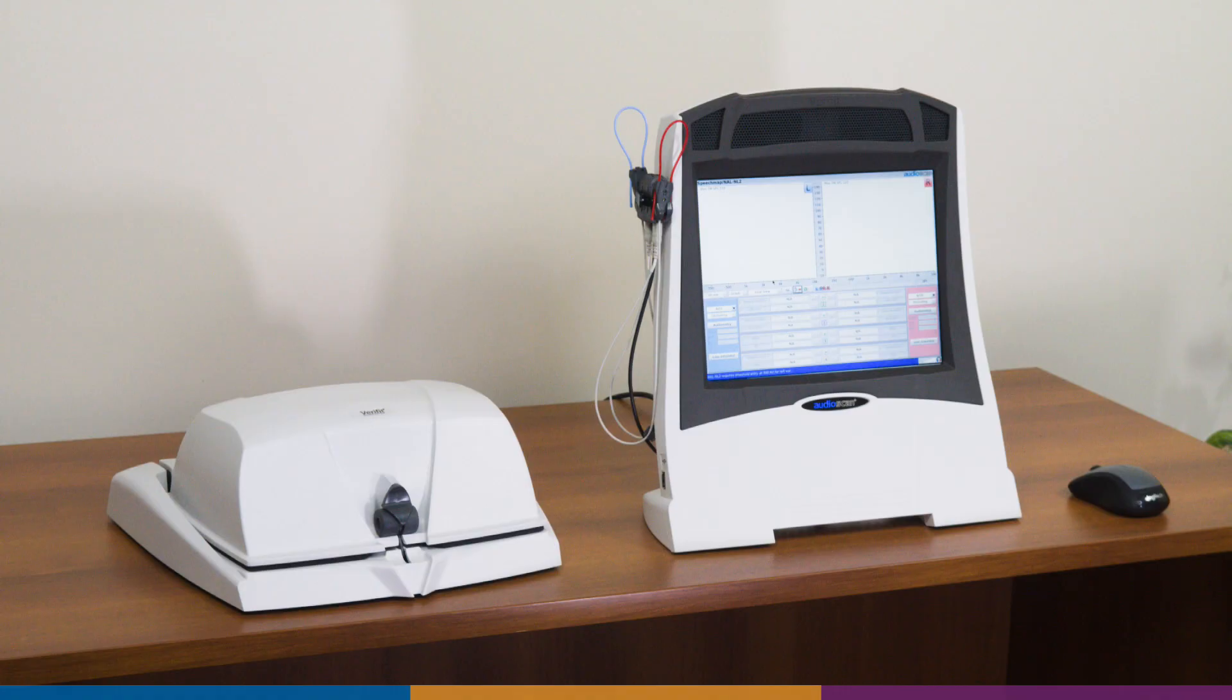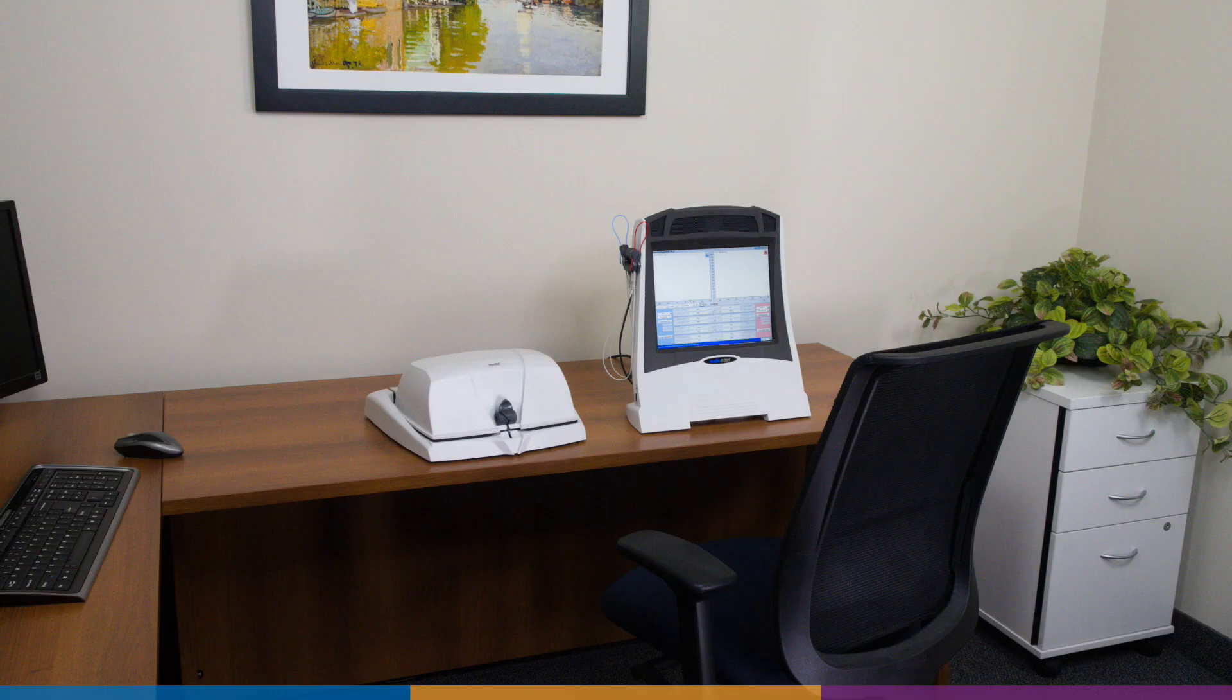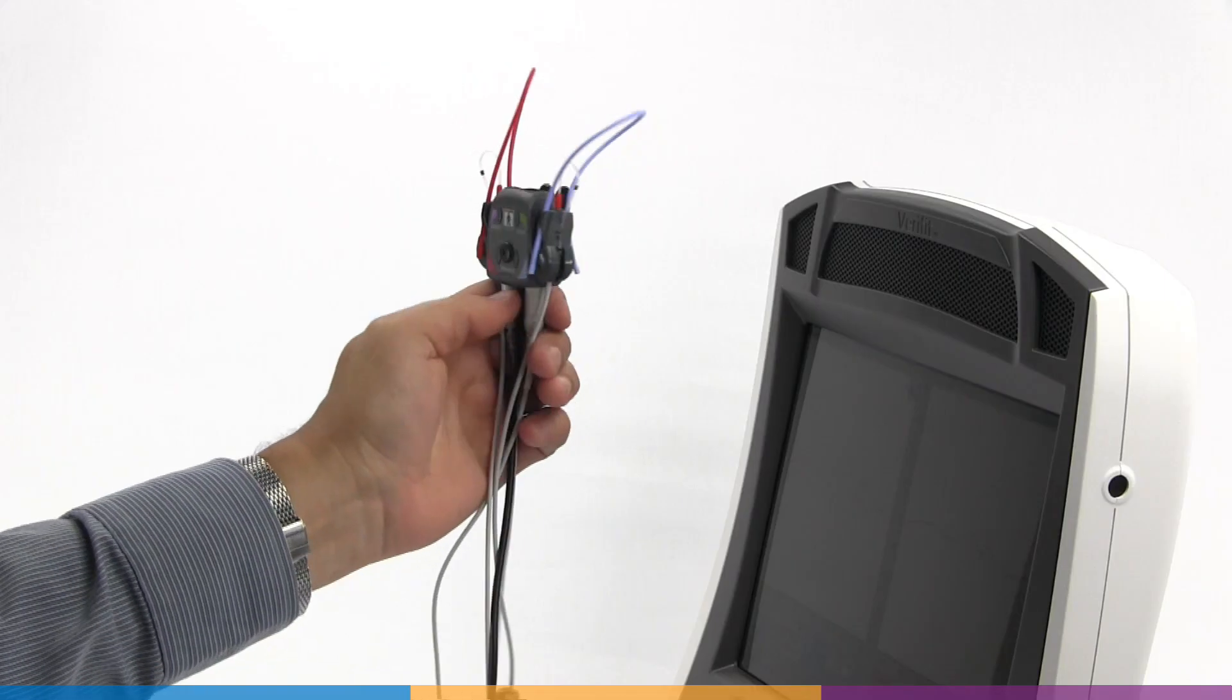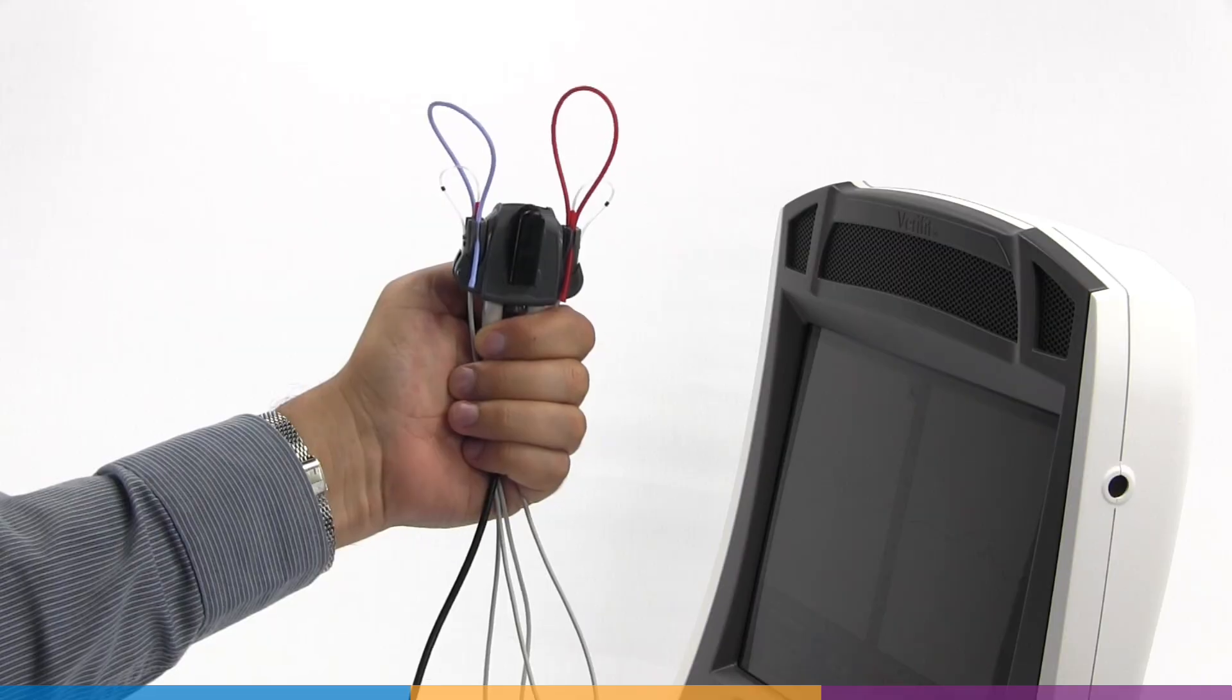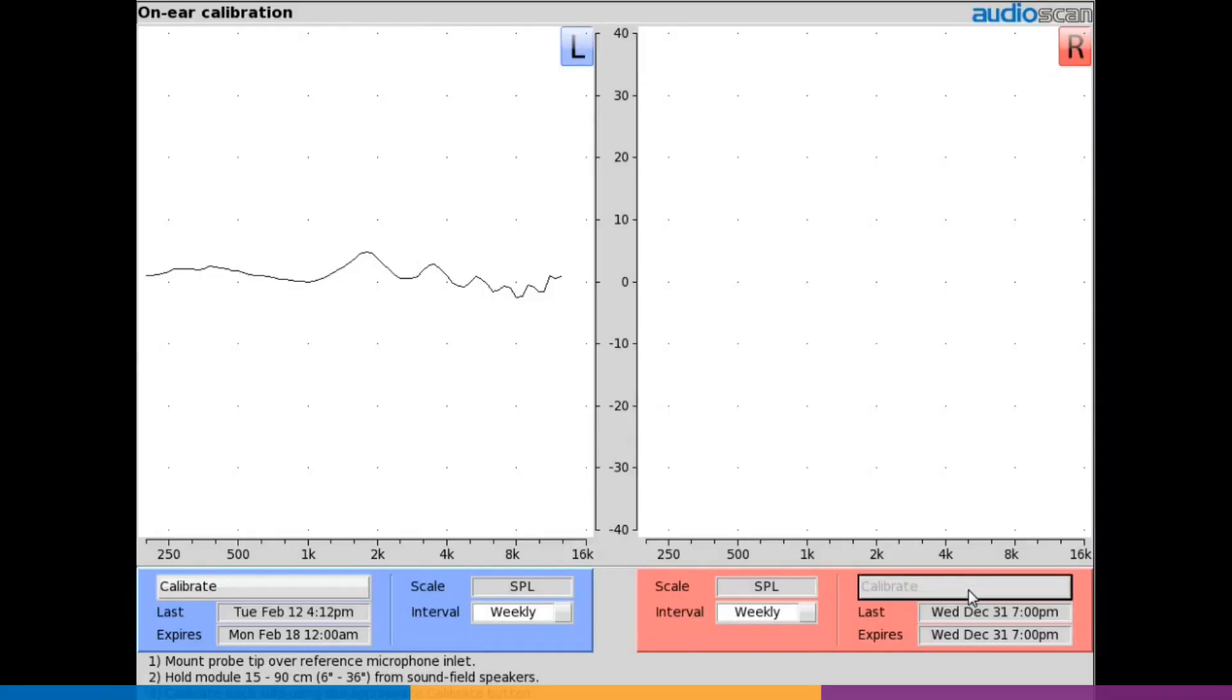Before using ProbeGuide, ensure that your equipment is ready for real ear measurements. Your Verifit2 or Axiom should be positioned away from reflective surfaces in a quiet environment and have a valid probe microphone calibration, according to recommendations in the UserGuide.